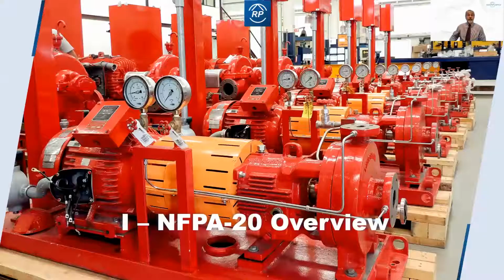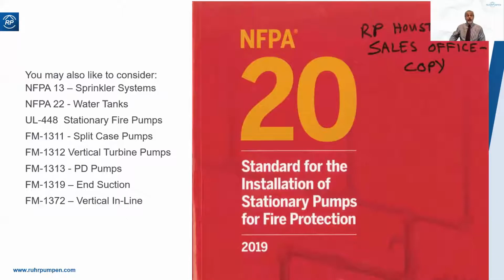So first, NFPA-20, National Fire Protection Association Standard number 20 for the installation of stationary pumps for fire protection. That's the pamphlet you ought to go out and buy. You might also like to consider buying NFPA-13 for sprinkler systems and 22 for water tanks. And if you're really interested, you could get the UL and FM standards that have sprung out of this NFPA-20.